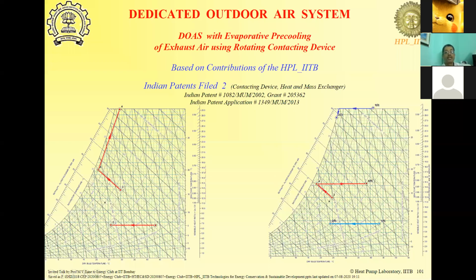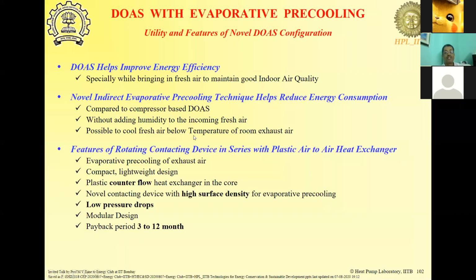Okay, so the advantages of DOAS with evaporative pre-cooling. DOAS helps improve the energy efficiency, especially while bringing fresh air to maintain good indoor air quality. Novel indirect evaporative pre-cooling techniques help reduce energy consumption compared to compressor-based DOAS without adding humidity to the incoming air. It is possible to cool fresh air below the temperature of the room exhaust air, that is, the room dry bulb temperature.